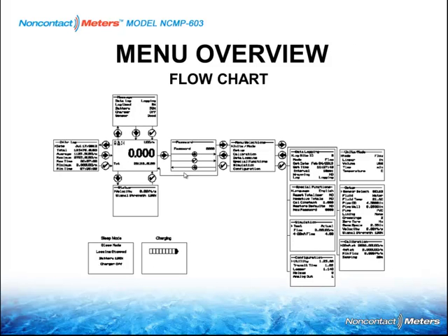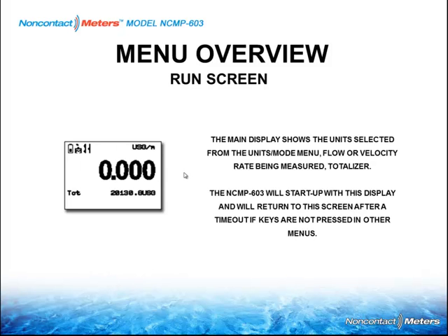In the manual, of course, is a flow chart, and this is basically the methodology to use to program the flow meter. Nothing really unique. You just put in the pipe statistics and the application statistics, and it gives you your spacing, and away you go. So when all else is lost, you don't really need to read the manual to operate this meter, but this is the pathway to program the device.